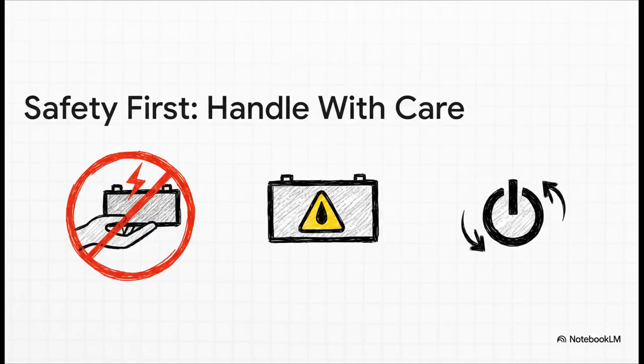And finally, a super important word on safety. A UPS is not just a heavy power strip, it is a serious piece of electrical equipment. There's a real risk of shock from the energy stored in its capacitors, even when it's completely unplugged from the wall. The batteries can be a hazard, with spilled electrolyte, and its automatic controls can kick on when you least expect it. So please, always handle them with care and follow the manufacturer's instructions.